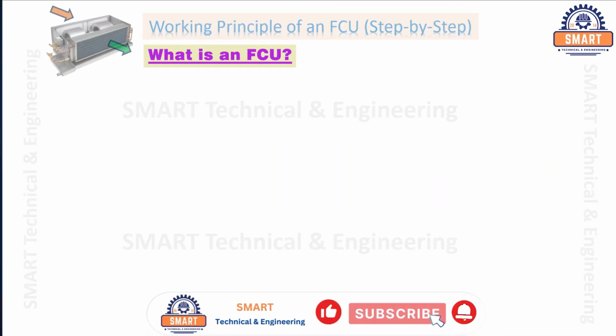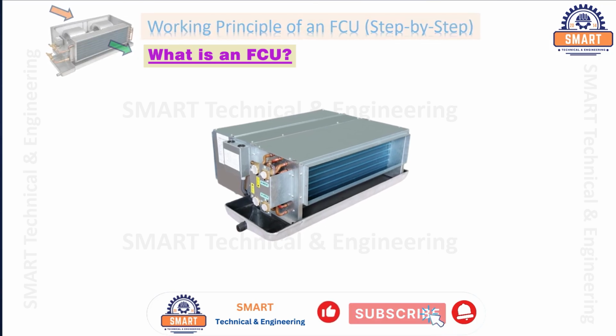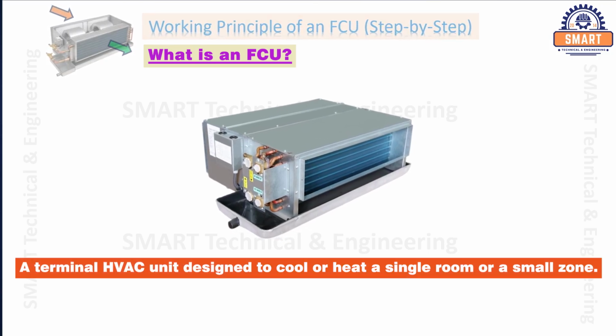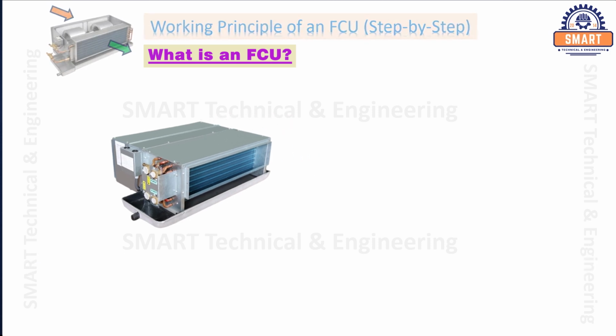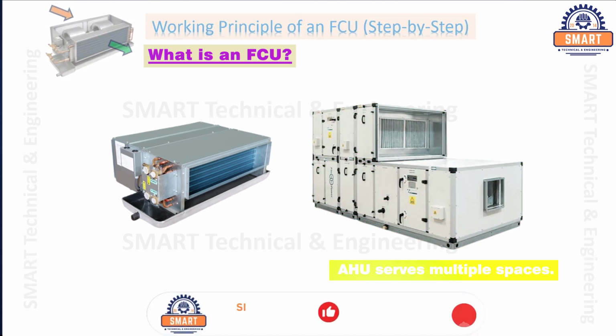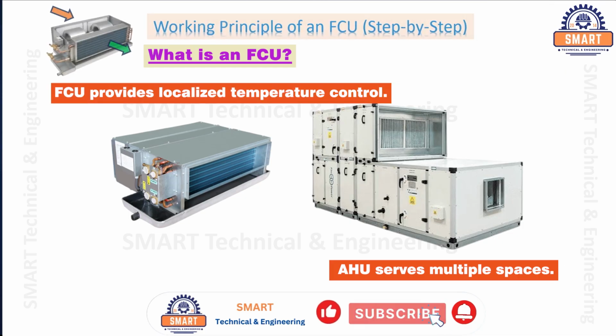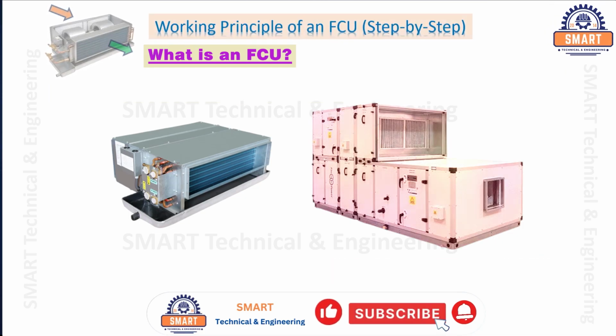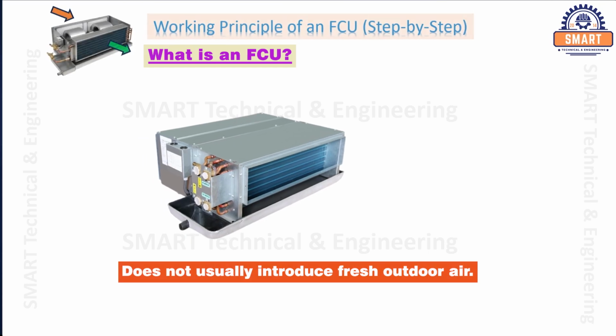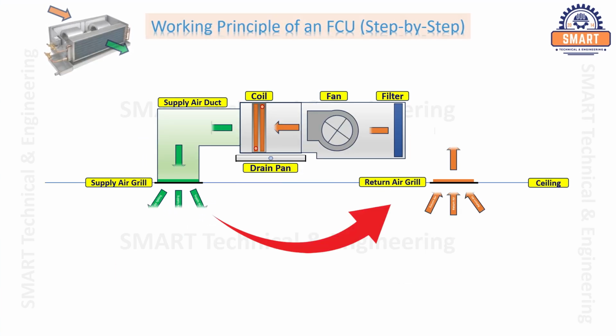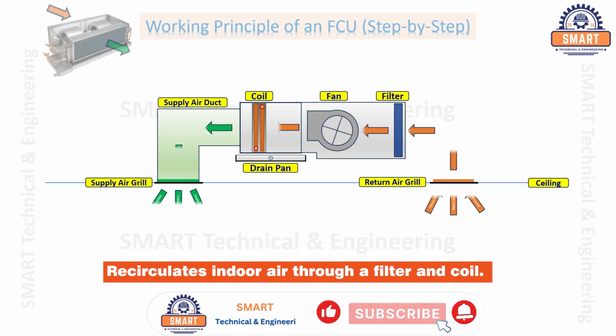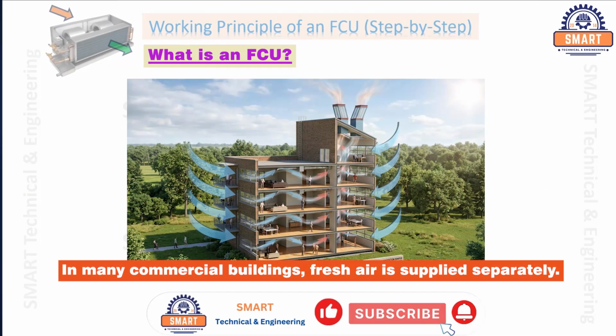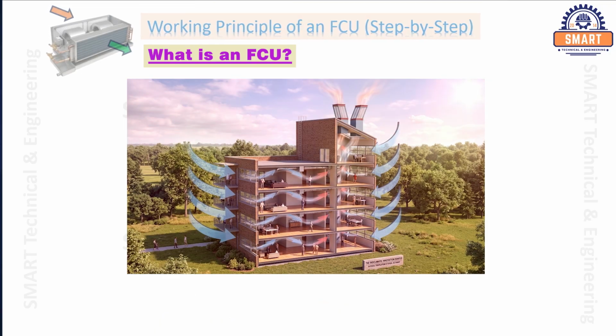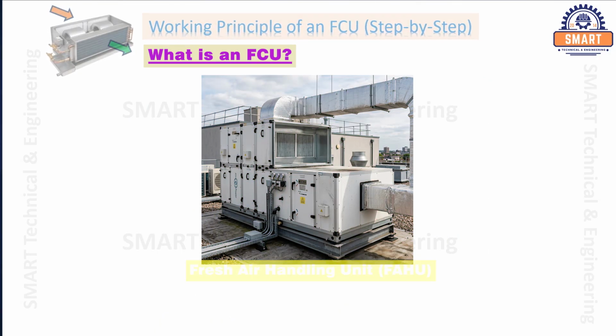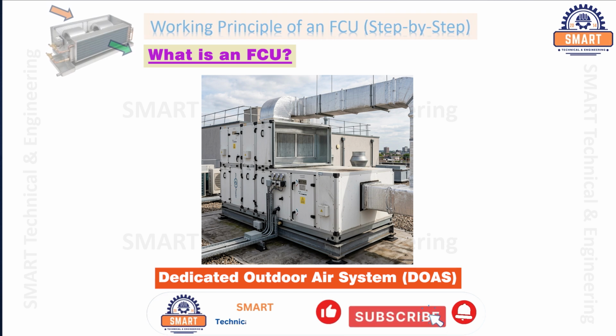What is an FCU? A fan coil unit, FCU, is a terminal HVAC unit designed to cool or heat a single room or a small zone. Unlike an air handling unit, which serves multiple spaces, an FCU provides localized temperature control. An FCU does not usually introduce fresh outdoor air. Instead, it recirculates indoor air through a filter and coil. In many commercial buildings, fresh air is supplied separately by a fresh air handling unit, FAHU, or a dedicated outdoor air system, DOAS.